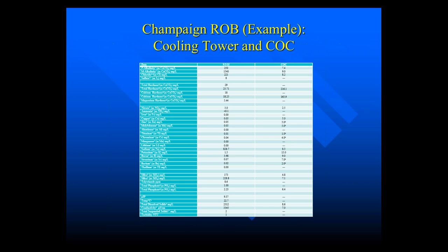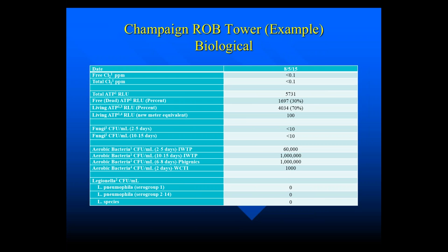It's a full analysis. For the cooling tower we again did a full analysis and then calculated the cycles of concentration of each of the components. For biological testing, we tested chlorine, total ATP, and free ATP — the difference between total and free giving us the living fraction. All the reports record just the living ATP. We transposed older data to be equivalent to our new, more sensitive meter. We also tested for fungi and aerobic bacteria, taking samples read after two to five days and then again at 10 to 15 days, because some bacteria take longer to develop.